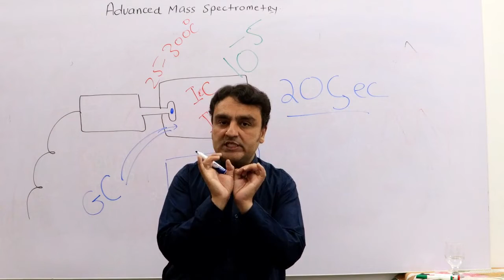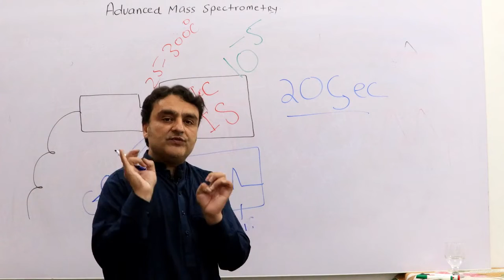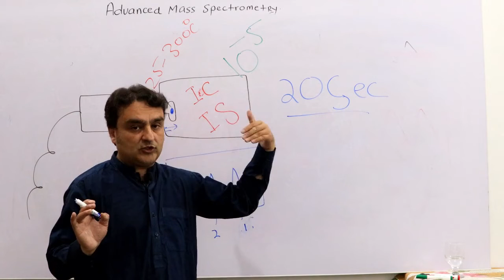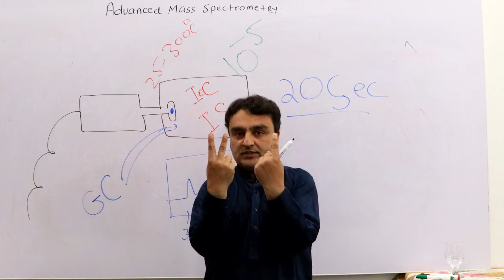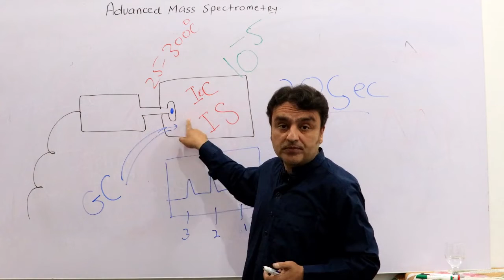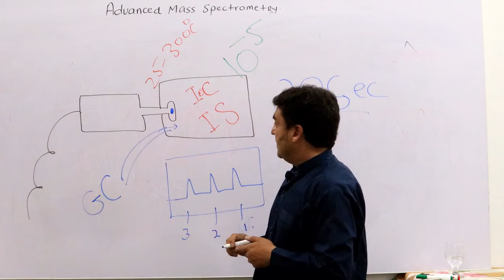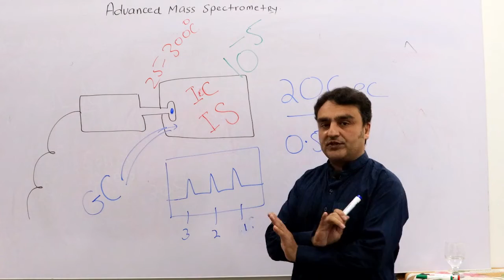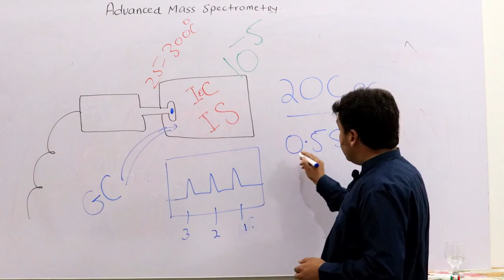Okay, 20 seconds. In 20 seconds you can get your spectrum on the screen. The other time will be taken because you will be printing it in 5 or 6 seconds, but that's not counted. So the analysis time for a sample in a typical electron ionization mass spectrometer is 20 seconds. But when it is attached to the GC, now because in the GC many compounds are coming one after the other in just some seconds, the instrument should be quite faster. It should have a fast analyzing time, of 0.5 second. In 0.5 second the mass spectrometer should give you the spectrum, or otherwise everything is messed up. You will get a mixture. Even less than 0.5 seconds would be even better.